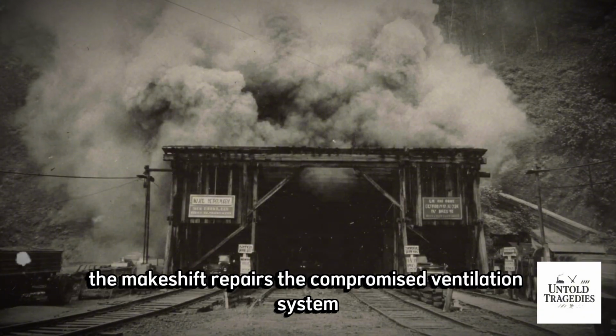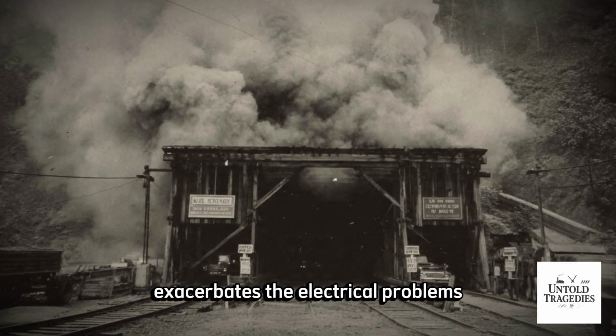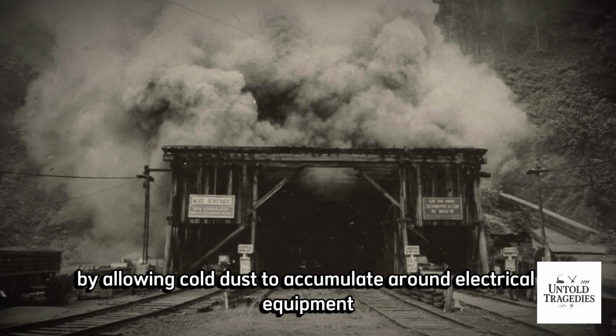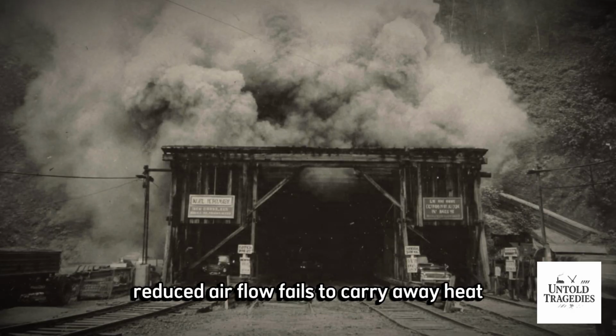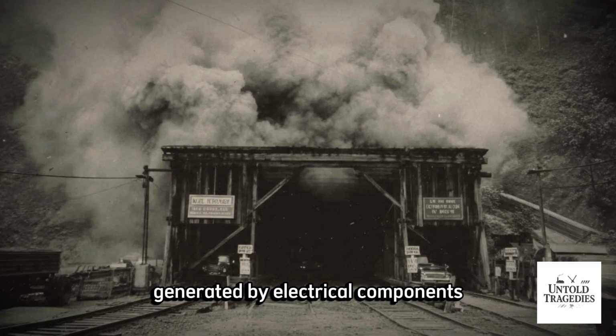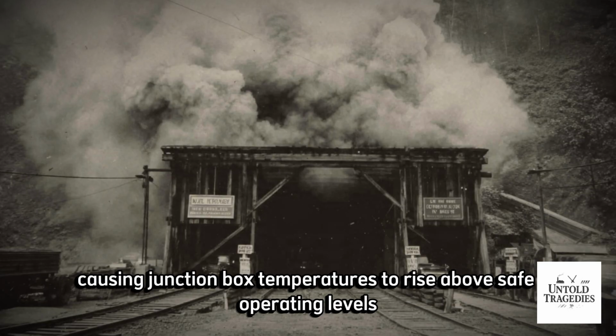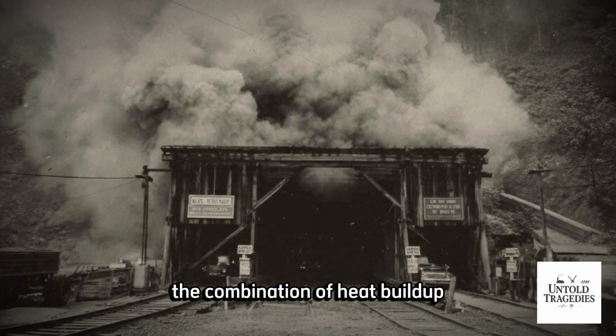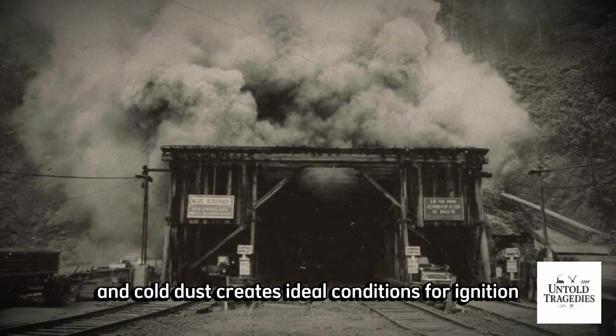The compromised ventilation system exacerbates the electrical problems by allowing coal dust to accumulate around electrical equipment. Reduced airflow fails to carry away heat generated by electrical components, causing junction box temperatures to rise above safe operating levels. The combination of heat buildup and coal dust creates ideal conditions for ignition.